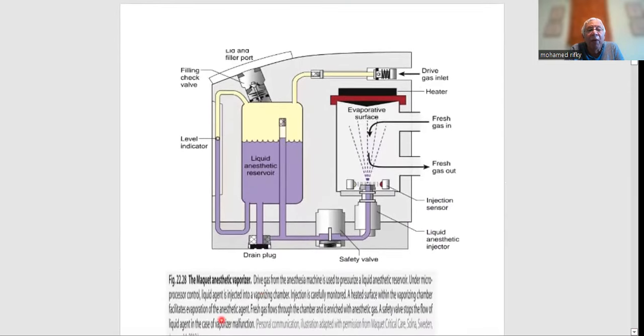This figure shows the Maquet, as we said before, a direct injection of the vapor into the circulation to the patient directly. So the Maquet injector, the working principle, as you can see, this is the container containing the liquid.